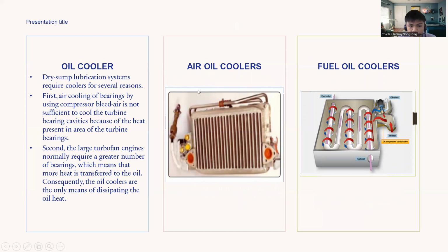This is what an air oil cooler looks like, and this is how the fuel oil coolers look. The fuel inlet goes in the two tubes. It passes through the tubes. It goes out in the fuel outlet. As the fuel goes in the tubes, the oil temperature control valve controls the temperature of the oil around the tubes, and the oil returns back to the oil pump.